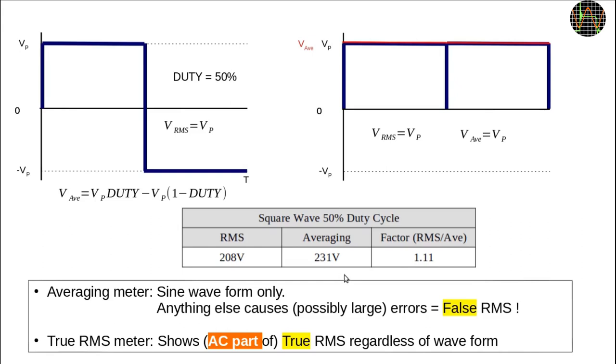Which is exactly what we saw earlier when comparing true RMS and averaging meters. So the key difference between an averaging and a true RMS meter is that for an averaging meter everything is a sine wave and if it is not the results are generally wrong by a varying amount which can get quite large. For non-sine waveforms the averaging meter shows a false RMS. A true RMS meter instead produces an accurate result of the AC part of the RMS taking the waveform into account.